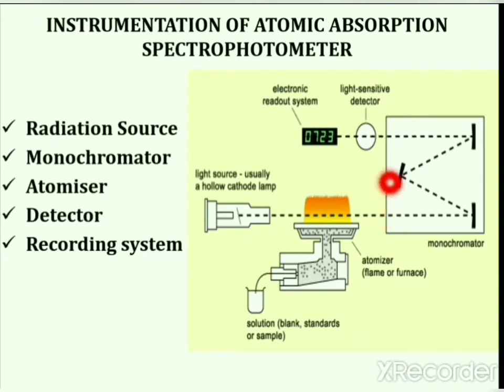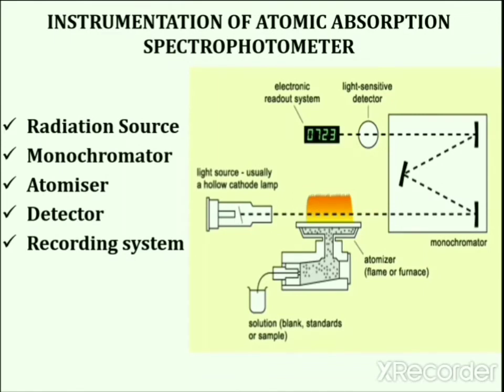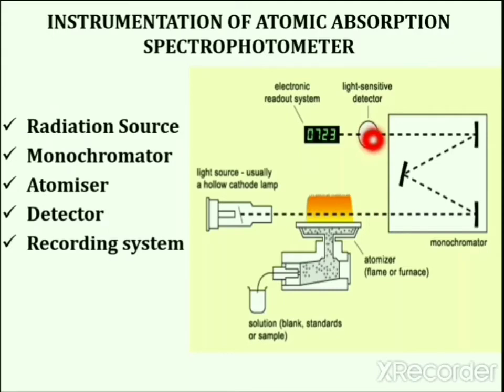The key elements of a conventional atomic absorption spectrophotometer are: a line source of radiation; an atomizer, of which there are two types — flame and furnace; a monochromator; a detector for measuring the intensity of radiation passing from the sample; and a recording system. Other components include optics such as lenses and mirrors that relay and focus light through the sample and into the detector.